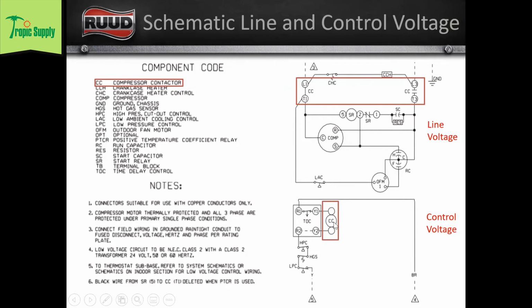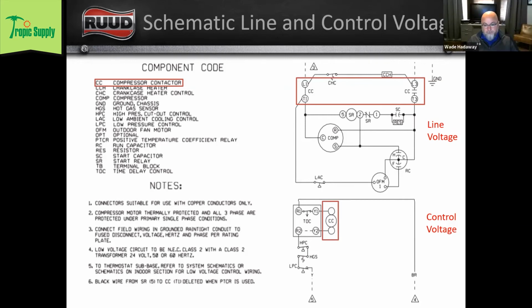So we've got both low voltage on the bottom and high voltage on the top, but they are the same component, right? Contactors, relays, sequencers. There are a lot of components out there that have both high and low voltage parts to them. But when you look at the schematic, they're going to be split up between your line voltage and your control voltage, your load voltage and your control voltage.